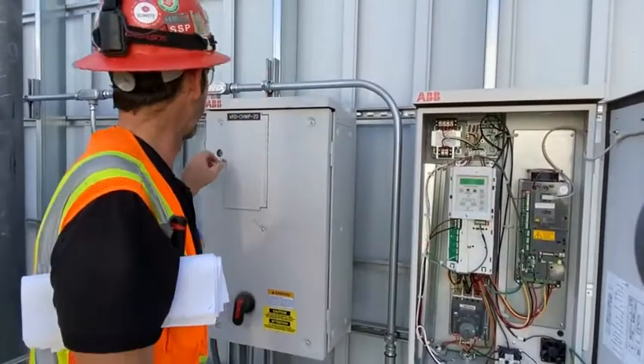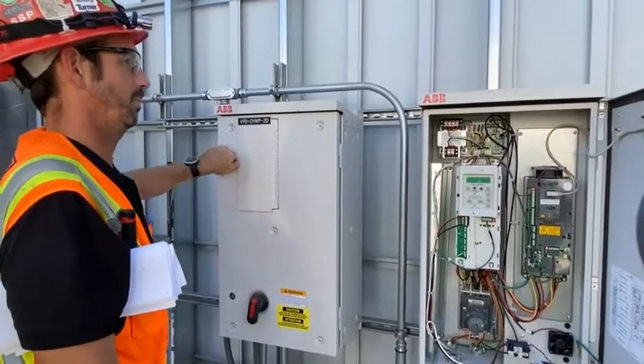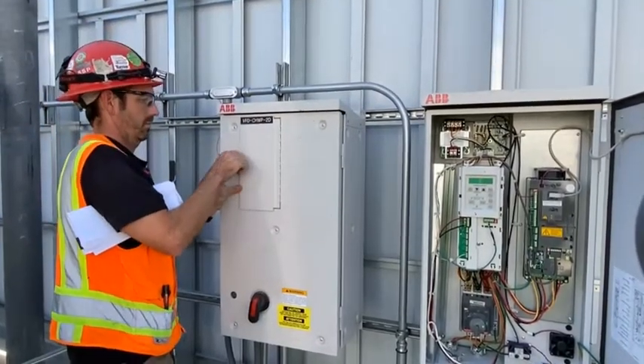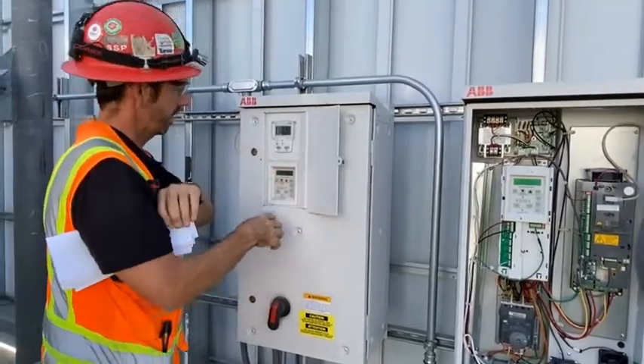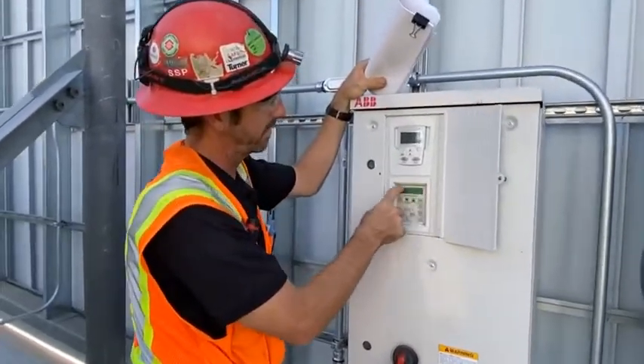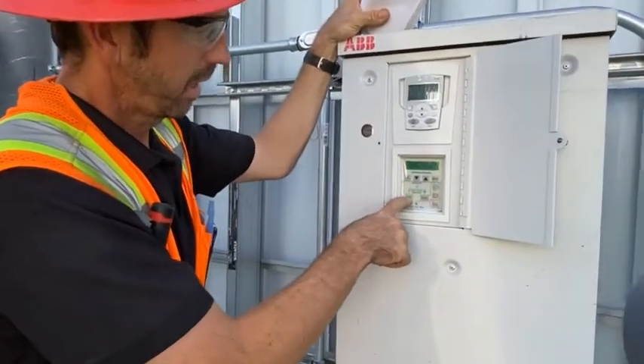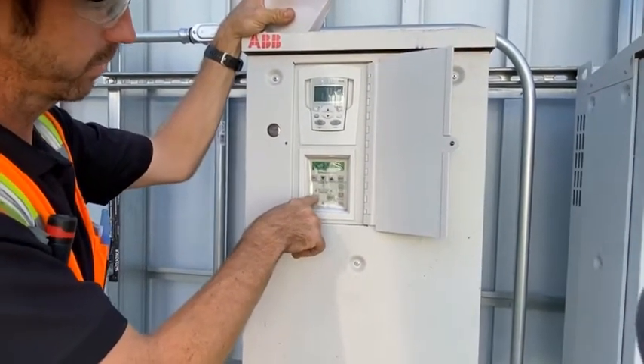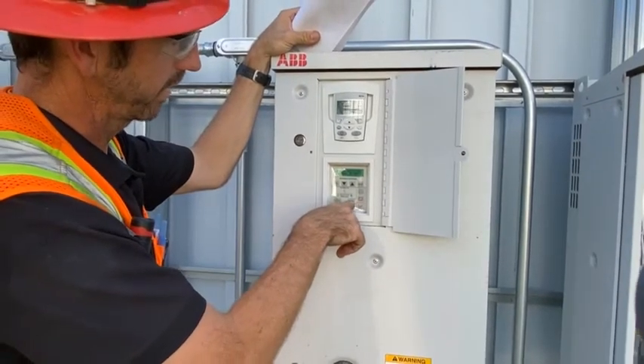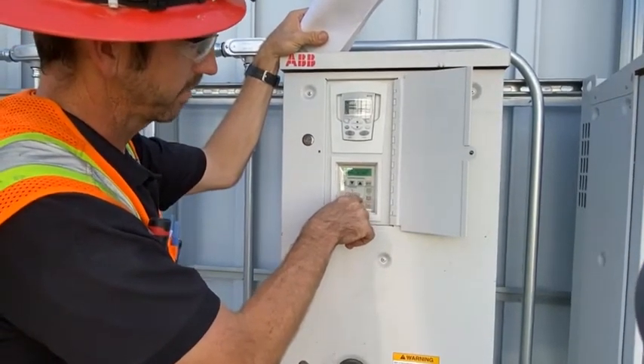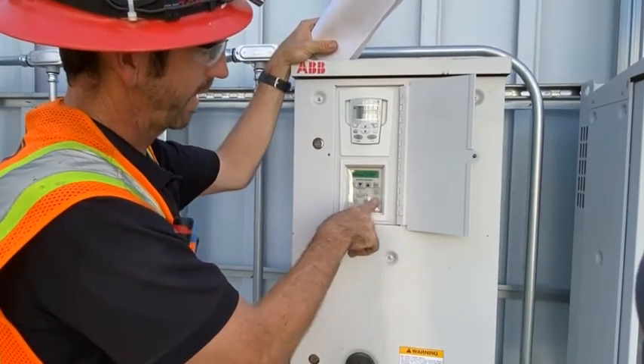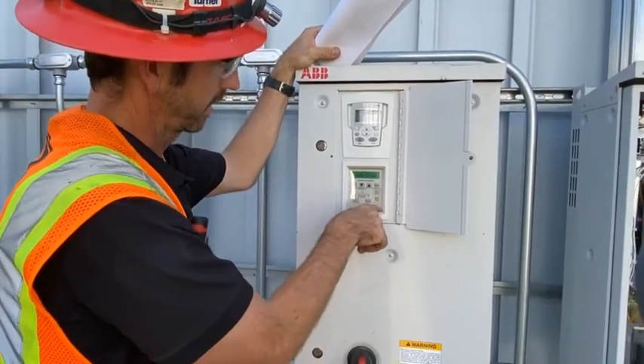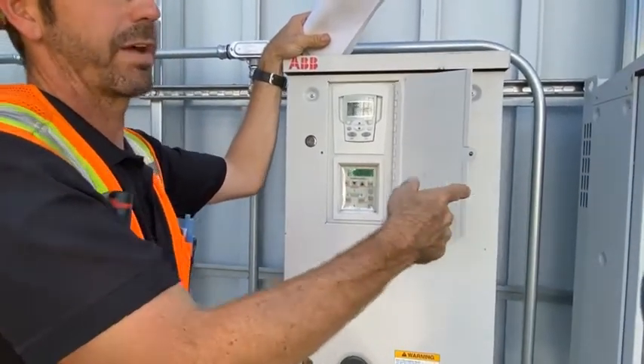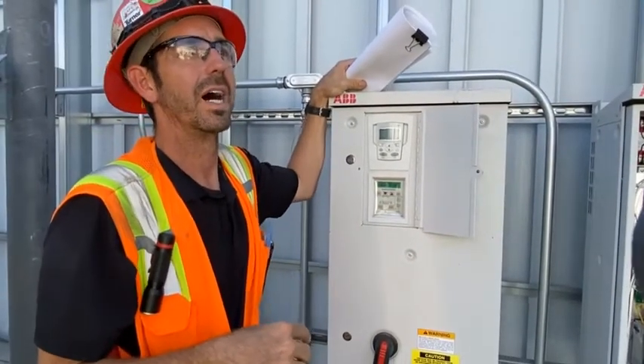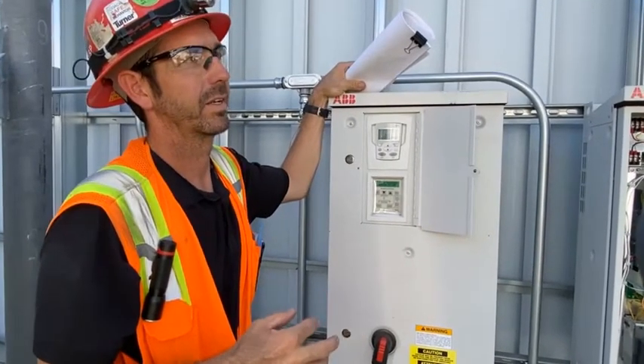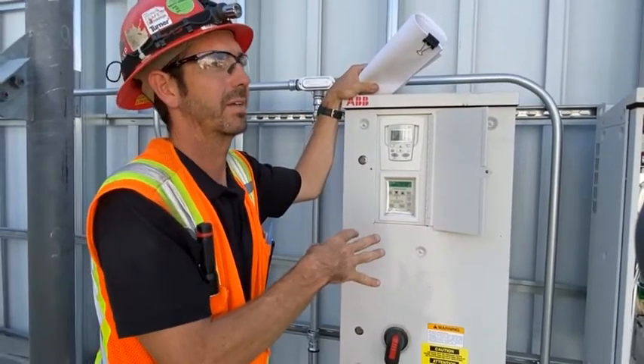And that's controlled by these buttons over here. This is called an Eclipse bypass interface. On the left side, it says drive. We have a green light, so we're in drive mode. On the right, it's bypass mode. There's no light on, so we're not in bypass mode. This is how you would turn it on and off in bypass mode or be in auto. Again, we don't want to use these unless you had a multiple drive failure. And even then, you've got to be careful using the bypass.